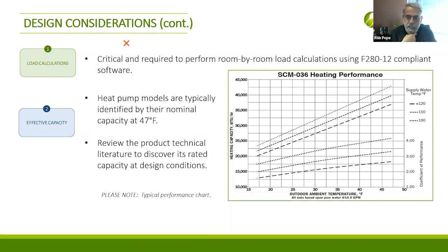F280-12 - that's a Canadian Standards Association standard, so it's CSA F280-12. That is the only accepted methodology. There are a handful of different programs you can use that utilize that methodology, but it has to meet that standard. And that is actually in the National Building Code and our BC Building Code as well. So anything other than that is just a guess - how much heat you need and how much cooling you need, room by room.